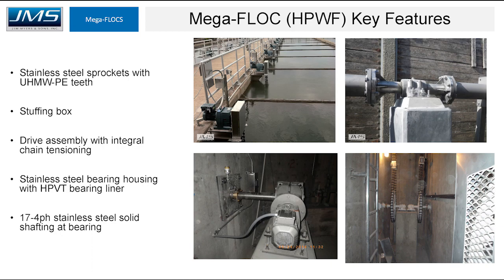There is a wet chain design, a dry chain design in a dry well, and a direct drive in a dry well straight through the wall through a stuffing box. Sprockets can be all stainless steel with UHMWPE. Submerged bearings are typically stainless steel housings with an HPVT composite bearing liner, which is a composite plastic material with Teflon impregnation, significantly increasing lifespan. The solid shafting running through the bearings is typically 17-4 PH stainless steel, a very hard grade that prevents abrasion issues.